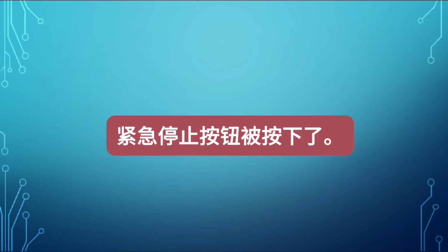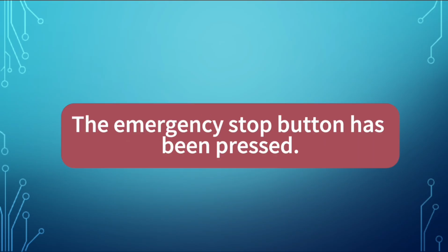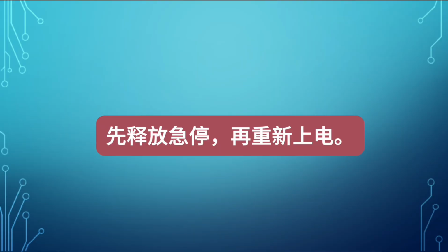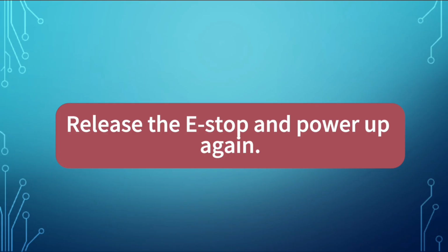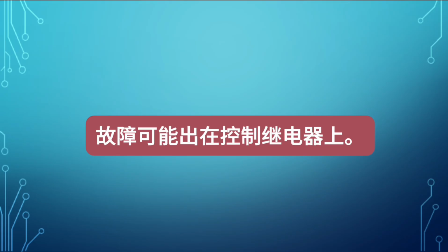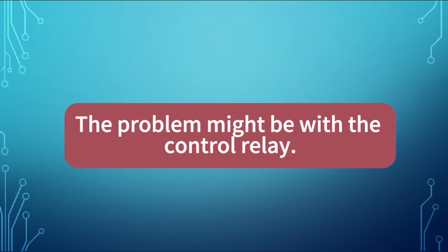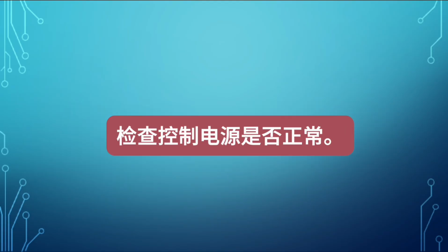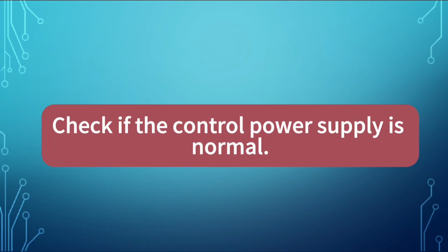The emergency stop button has been pressed. Release the e-stop and power up again. The problem might be with the control relay. Check if the control power supply is normal.